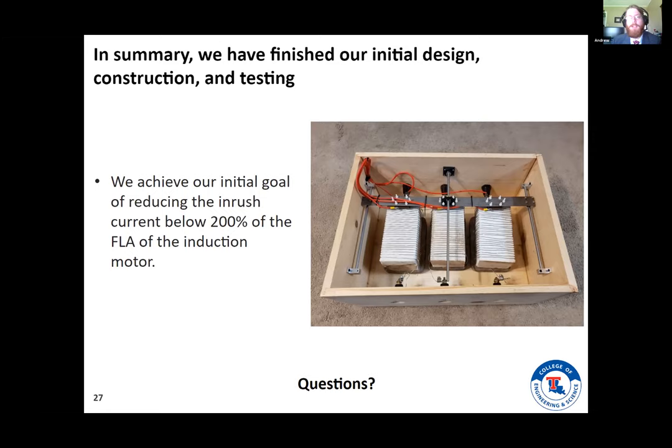So this would help with a couple of things. Mainly the acceleration of the motor would be a lot more smooth than other methods. That's what we were hoping to accomplish through the rheostat instead of using switching resistors. And that would prevent issues such as water hammer in the irrigation pipes from damaging the connected systems, or the stretching of belts in the conveyor systems.